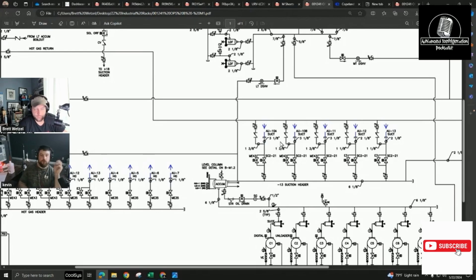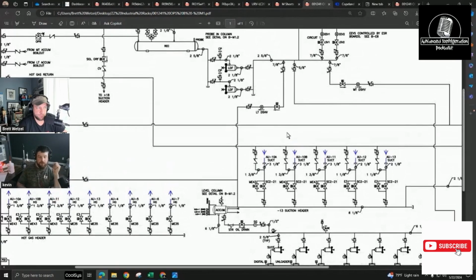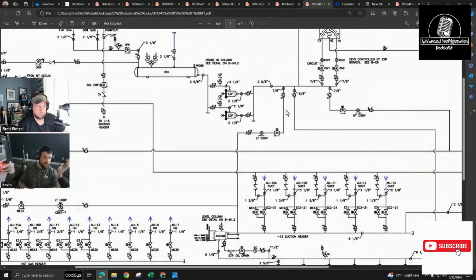When they do their CO2, they do hot gas down the liquid line, and it comes back on the suction and dumps either into the. God, I always say this wrong. Like it's this intercooler. So okay. It dumps into the intercooler, which is essentially an accumulator, and it's also the receiver for the low temp. On a lot of big systems, like a lot of industrial systems, they'll run the intercooler like that. So that way they could use the lower pressure, low temp liquid, or your liquid coming back, and supply your low temp circuits with it.